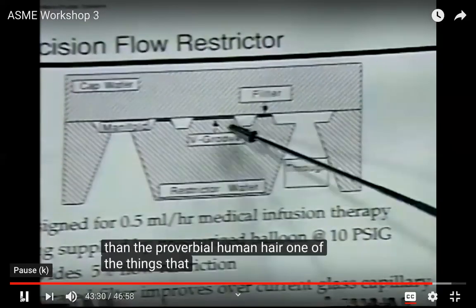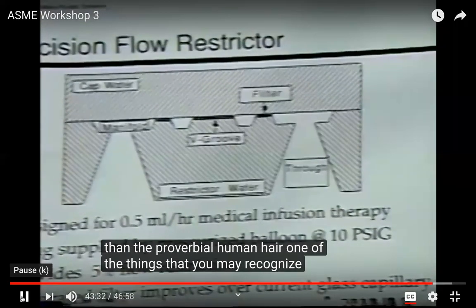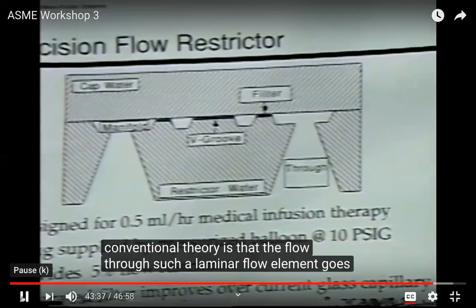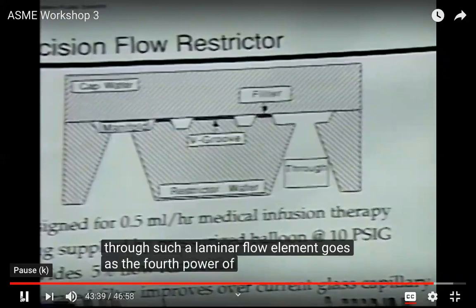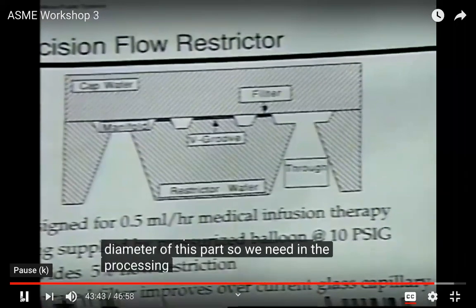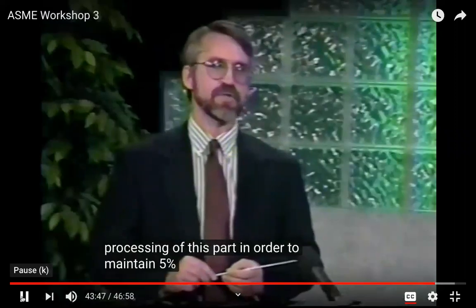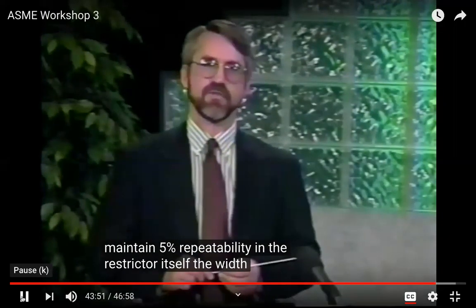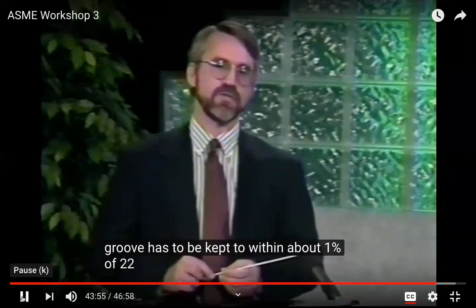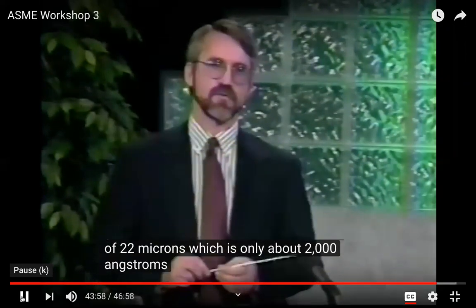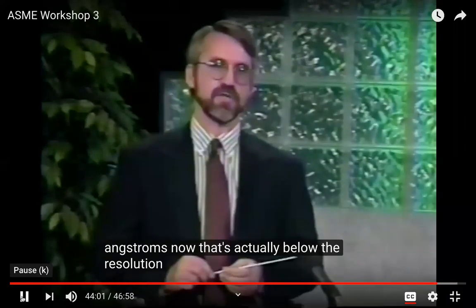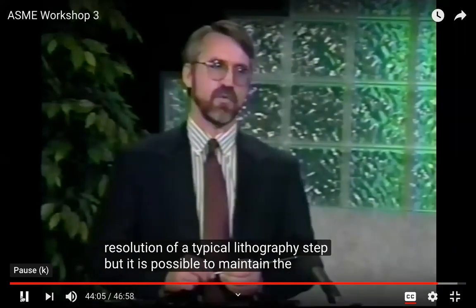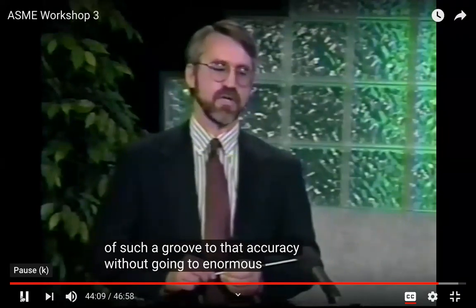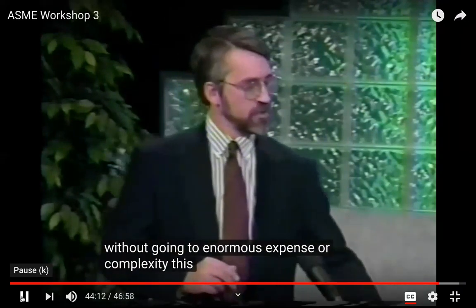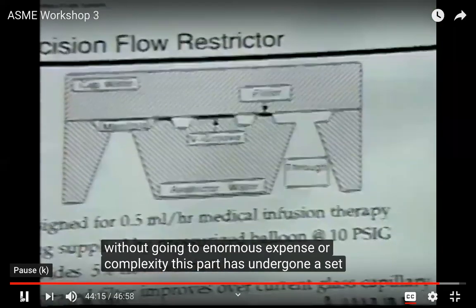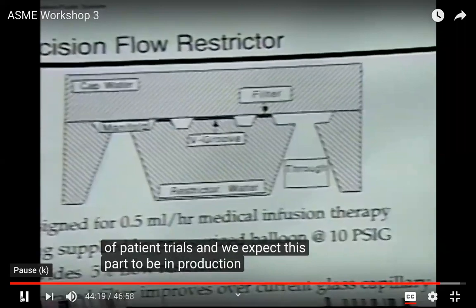One of the things that you may recognize from conventional theory is that the flow through such a laminar flow element goes as the fourth power of the effective diameter of this part. So we need, in the processing of this part, in order to maintain 5% repeatability in the restrictor itself, the width of this groove to be kept to within about 1% of 22 microns, which is only about 2,000 angstroms. Now that's actually below the resolution of a typical lithography step, but it is possible to maintain the width of such a groove to that accuracy without going to enormous expense or complexity. This part has undergone a set of patient trials, and we expect this part to be in production relatively soon.